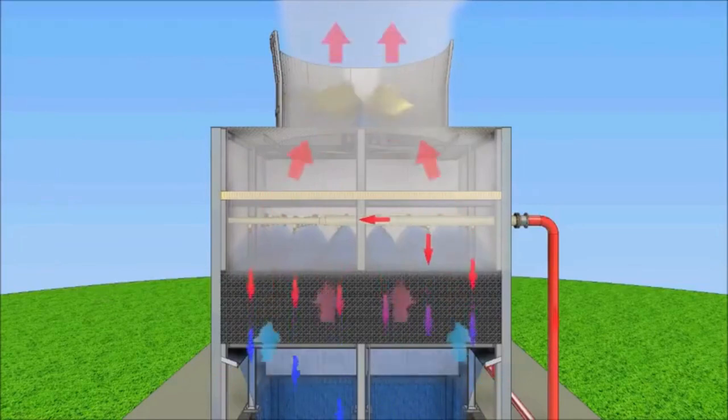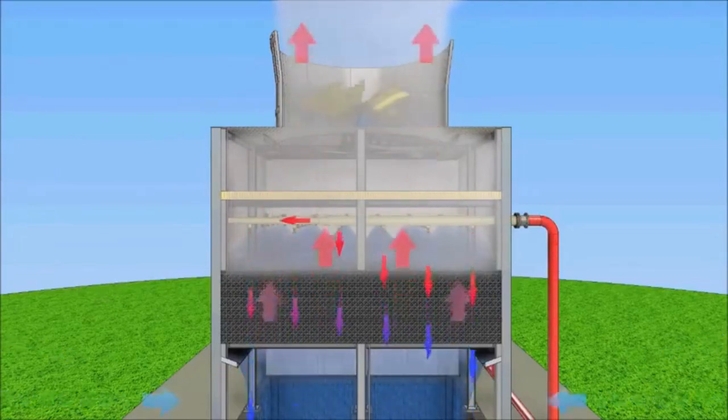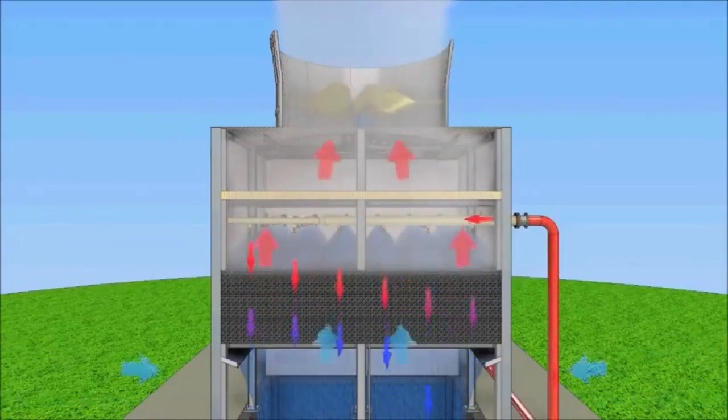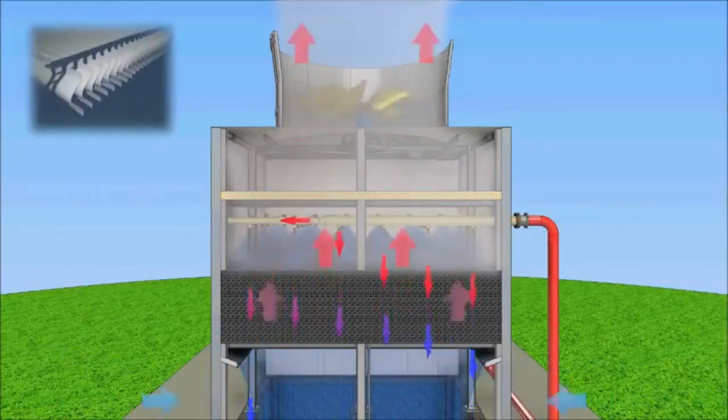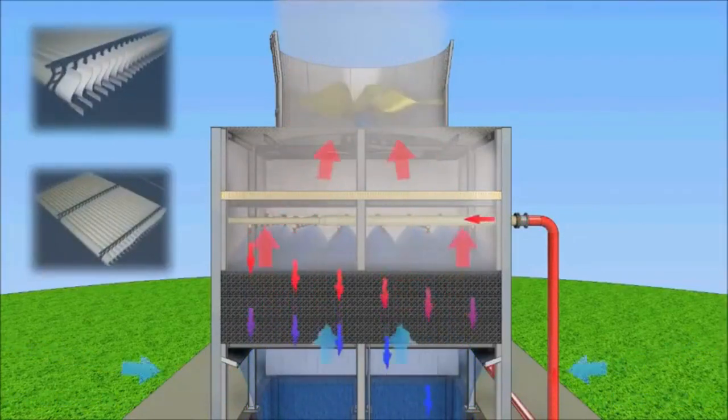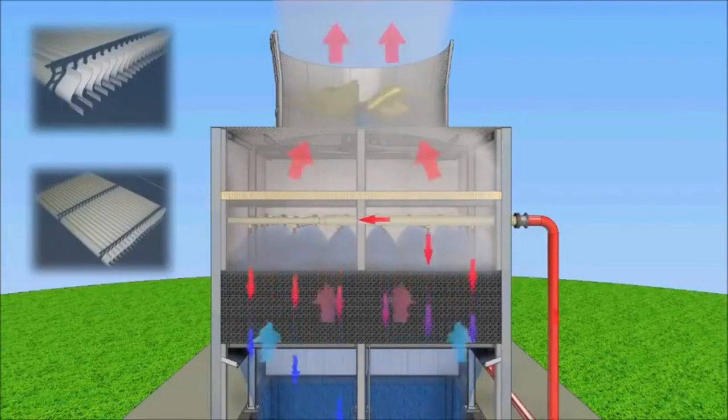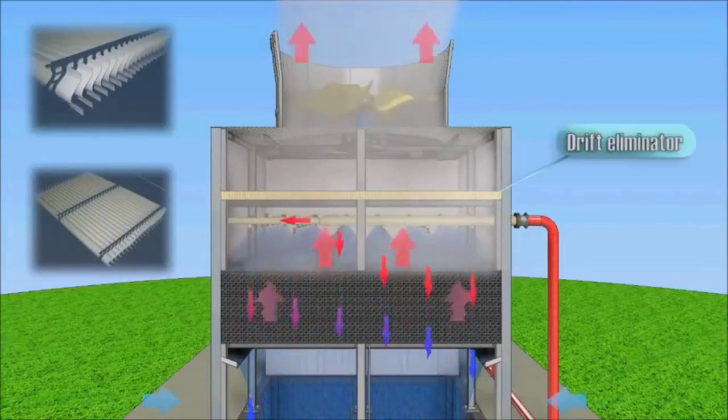Operating a cooling tower emits air saturated with water vapor and containing water droplets with size of 100-500 micron. To prevent entrainment of water droplets, above the water distribution system is installed a drift eliminator.